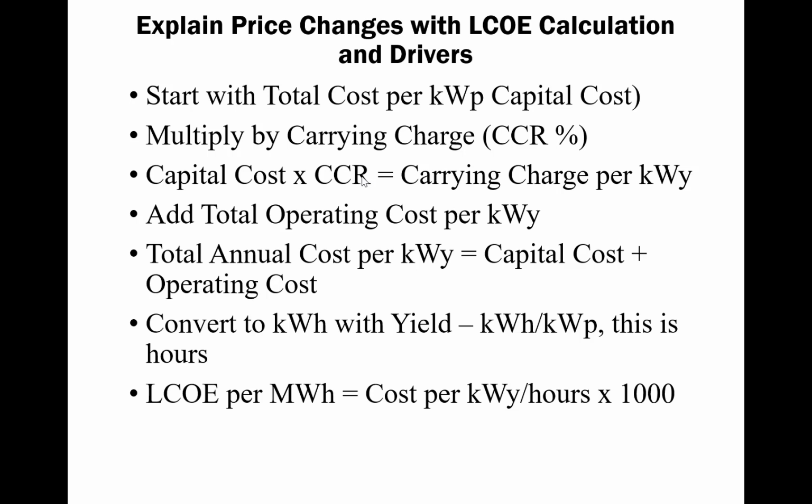It's not per kilowatt hour. It's per upfront kilowatt. And we take something called a carrying charge rate, and you don't get intimidated by this carrying charge rate one tiny bit. You just take this percentage, and then you can figure out what it is per kilowatt year. And then hopefully the operating cost is already stated per kilowatt year, and you get the total annual cost.